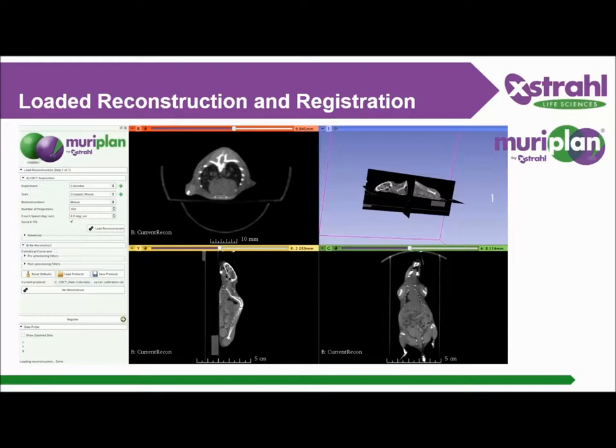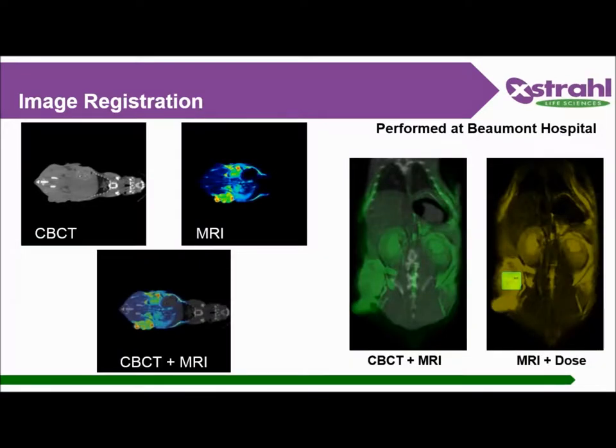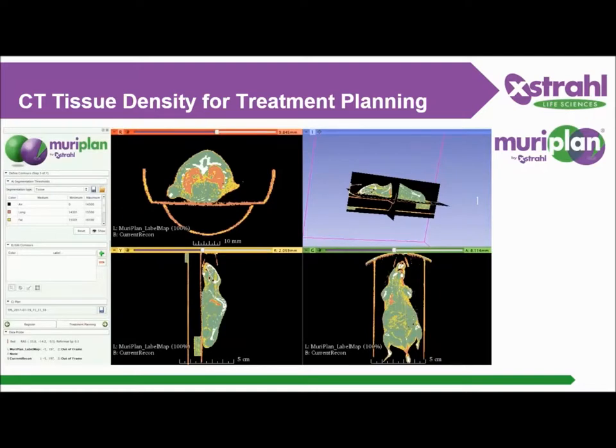Then you go to step number two: registration. In this step you have the possibility to co-register another CT, MRI, or basically any image modality in DICOM format. You can also skip this step and go directly to the segmentation module, which is a really easy step where the TPS does everything for you — it identifies five different densities from the CT grey level: bone, tissue, fat, lung, and air — and takes those volumes with different densities into account during beam calculation. You can save your plan at any point and come back to it later, or load it for a different mouse at one, two, or three weeks from now.